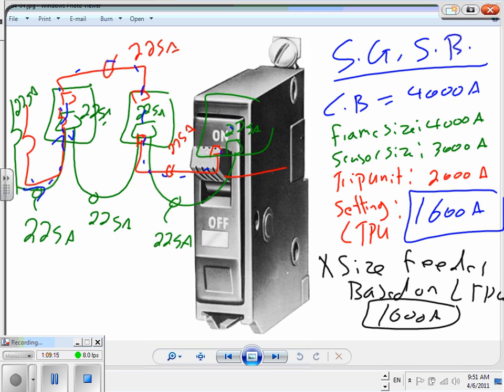The question, DJ, becomes: what if a wacko guy goes and resets this circuit breaker, up from 0.8 to 0.9? Now you increase the size. Well, usually these guys are under closed doors and supervised and so forth. But the code allows you to size the cable directly based on the long time pickup.